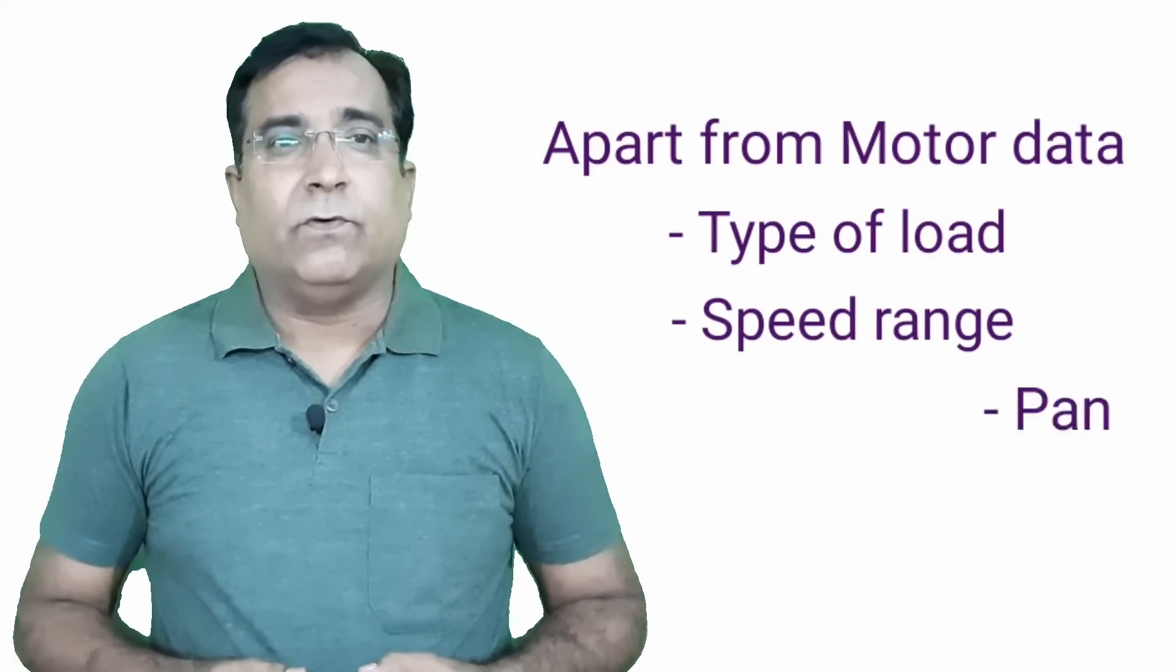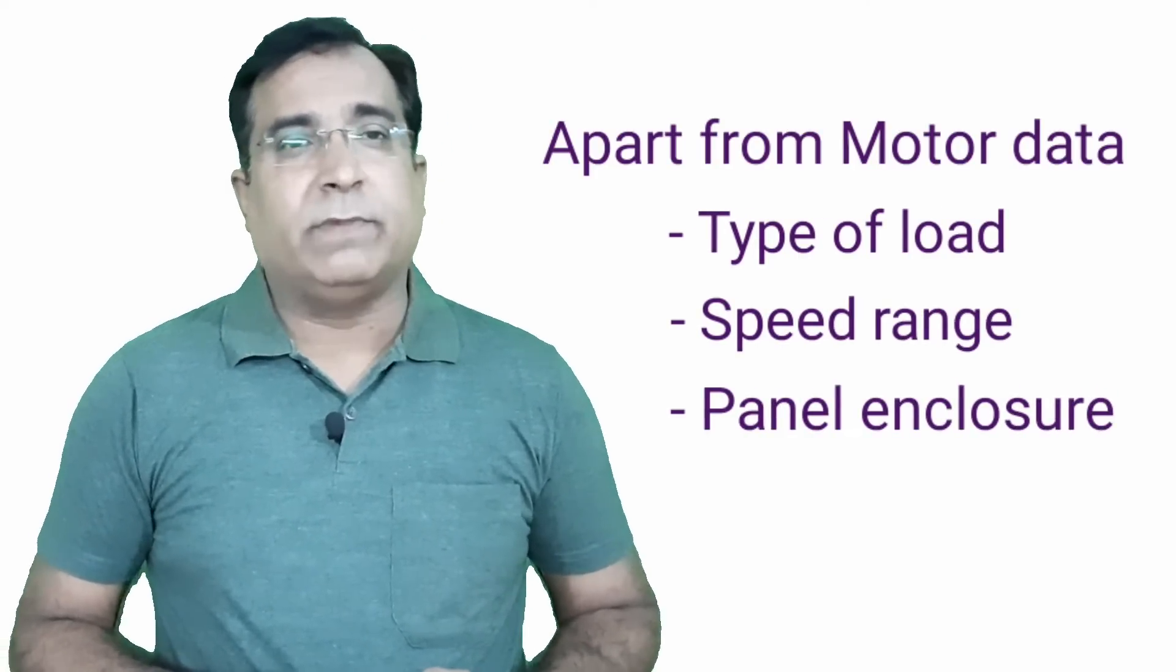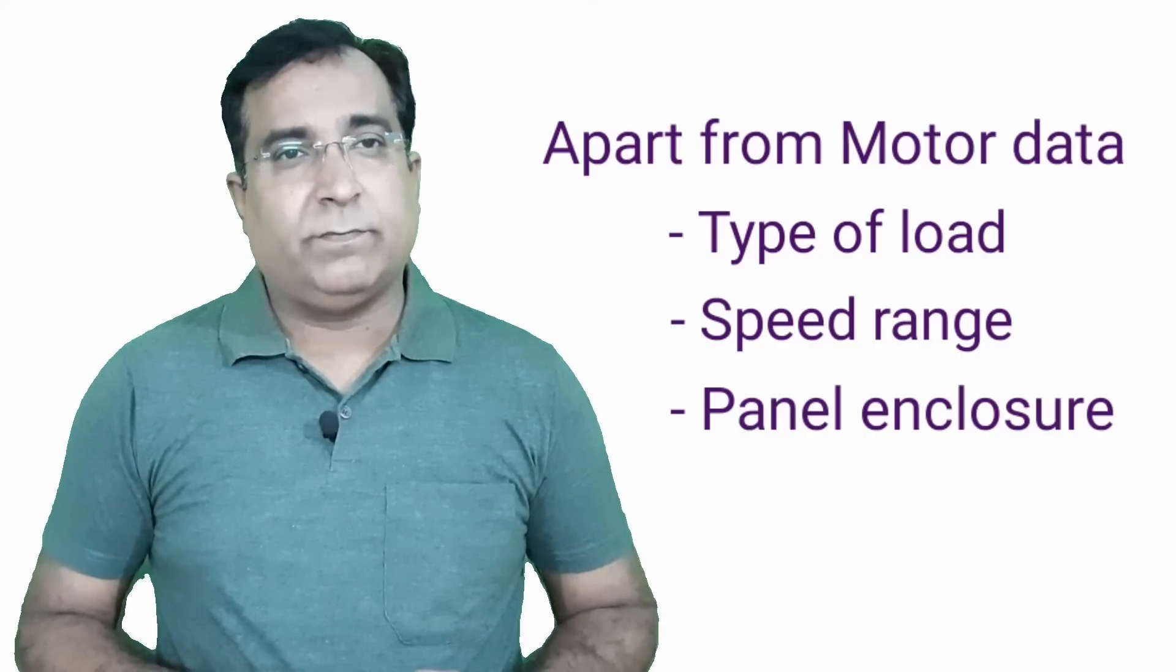When you go for selection of VFD, first of all you should collect information about motor data and system plus this info, type of load whether it is constant or variable torque, speed range, control method, or special enclosure for panel.